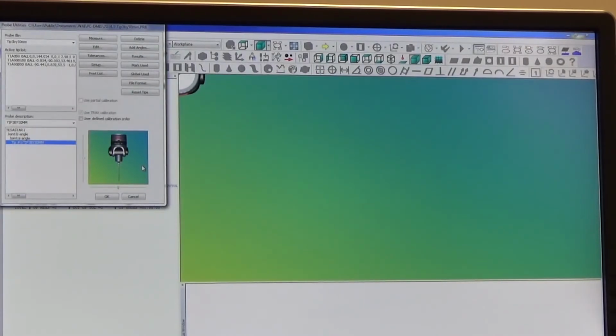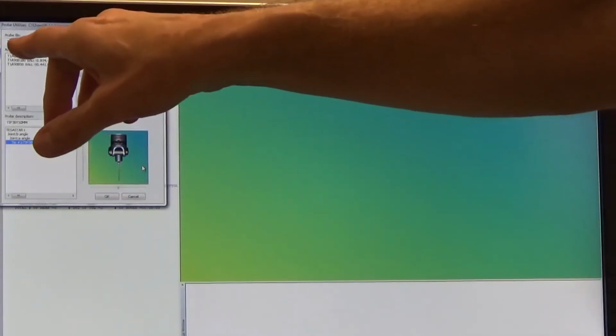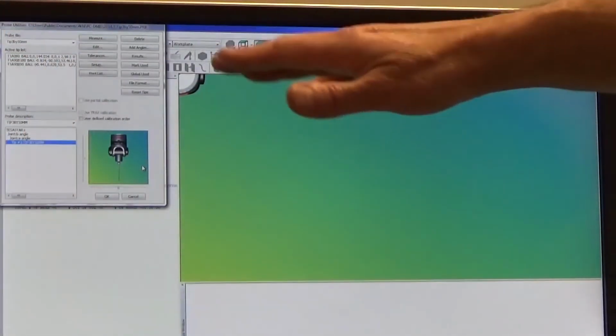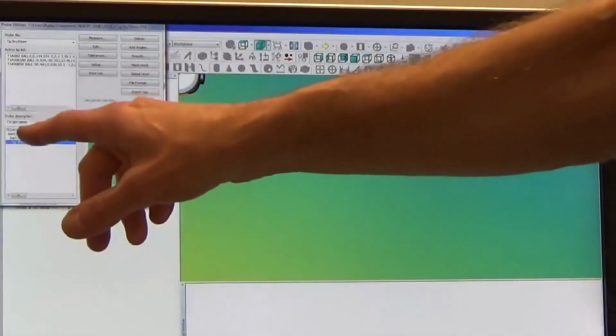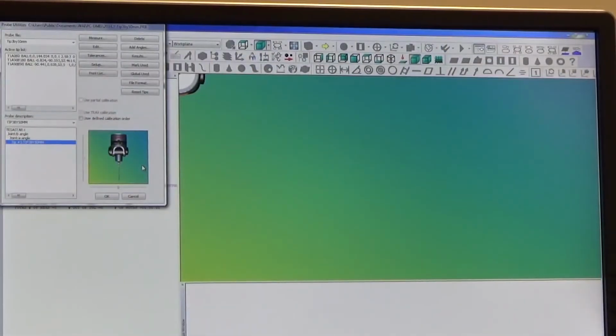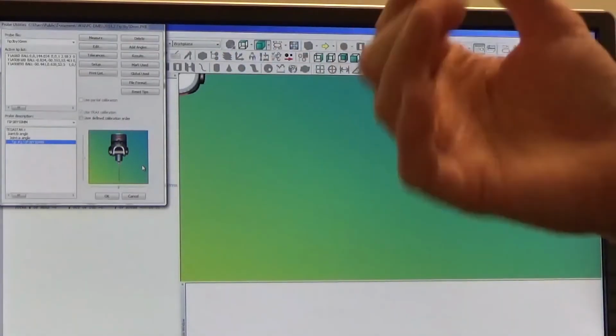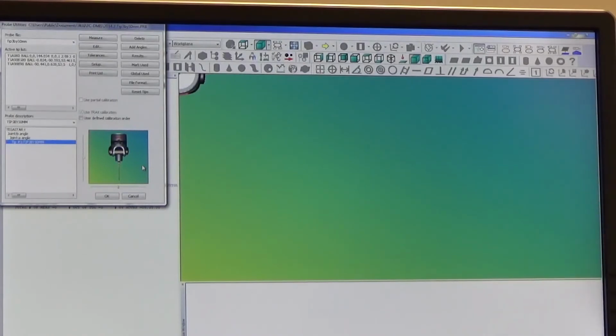The issue that we had was in my specification of this probe tip. I had not used this probe tip before, and I incorrectly had said this was a 4mm ball. It is in fact a 3mm ball. So given that all of the calibrations failed, that's a good indication that you have a setup issue. Something wrong with the way you specified the tip or any of the associated parts. If you had an automated wrist and if you have multiple probes, you would have to make sure that if you're changing probes during your operation that you've calibrated all the tips that you want to use. So in this case, we're good to go now. All I have to do is say OK, and we are set up.